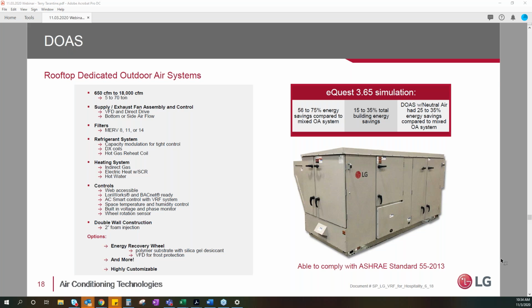Dedicated outside air systems: one thing that we do need to do with all these systems is to add fresh air, becoming a more and more important part in the COVID era. So I just want to point out that we do have to address the fresh air separately from the system. Again, it will tie in from a control standpoint, but we need to address fresh air. It's one advantage rooftops have, they have auto economizers that automatically bring in fresh air for us.